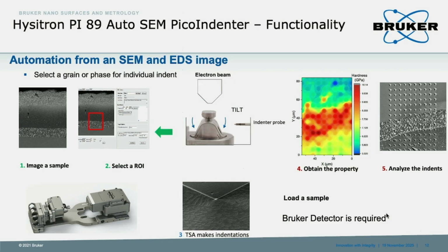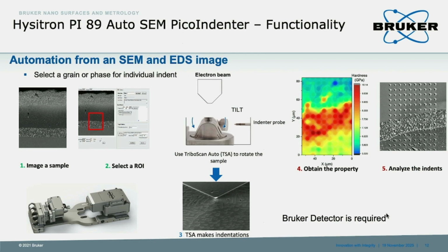This is what I showed in the video on the previous slide. In our Pico indenter, we have patented technology that allows you to install a rotating and tilted stage inside the SEM. You can import the SEM image here and see the SEM topography, then specify the area where you want to do the mechanical testing. The stage tilts to do the nanoindentation automatically, then goes back to see the post-test image.